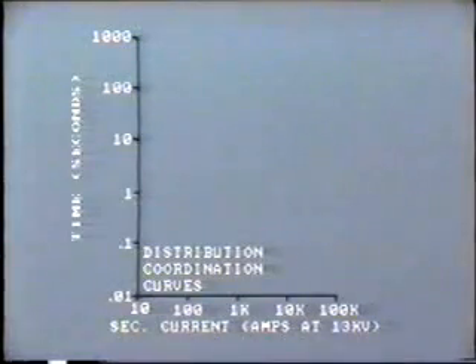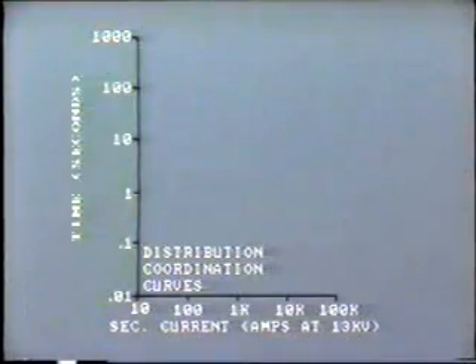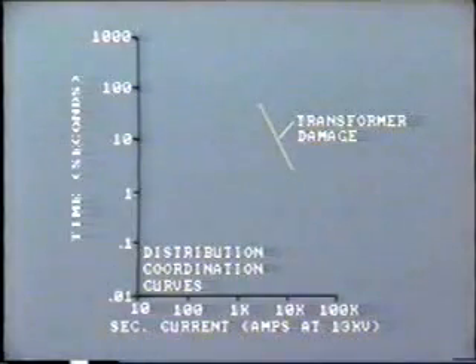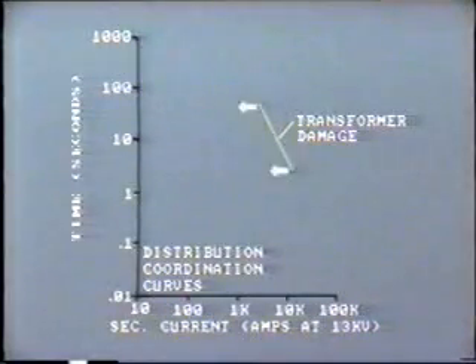Okay, so let's take a closer look at the coordination requirements for this circuit. The characteristics of the various protection devices are plotted on a log-log scale. This shows current along the base in amps and time in seconds along the vertical axis. We are concerned about protecting the transformer, so the first thing to plot is the transformer damage curve. We must make sure that all of the protective devices operate on this side of the transformer damage curve.